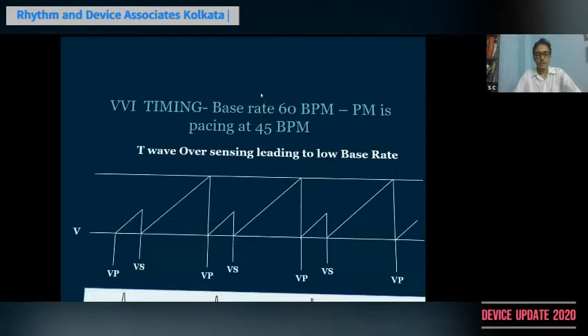So how do we do that? This led to the development of the concept of refractory periods. So the pacemaker decides that after a ventricular paced event, or any paced event for that matter, it will trigger a refractory period where any of these events will not be detected for a pre-specified interval. This is called the refractory period.